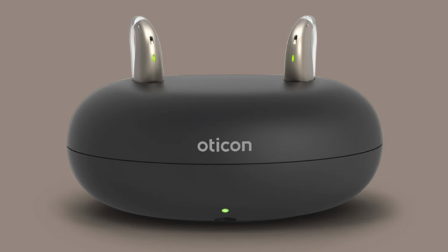But since most hearing aids sold today are rechargeable, chances are if you're having an issue with your hearing aids, it could be related to the lithium rechargeable battery inside of it. Most hearing aid manufacturers say that the rechargeable battery hearing aids are more durable than the disposable battery hearing aids, but I'm not buying it. A dead giveaway that there's an issue with the rechargeable battery inside of your hearing aid is that if you stick your hearing aids back into the charger and don't see anything light up.